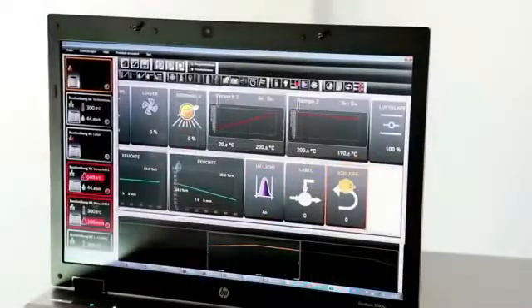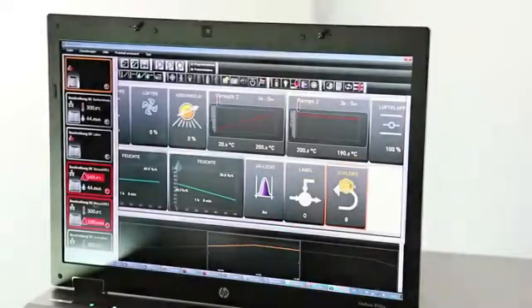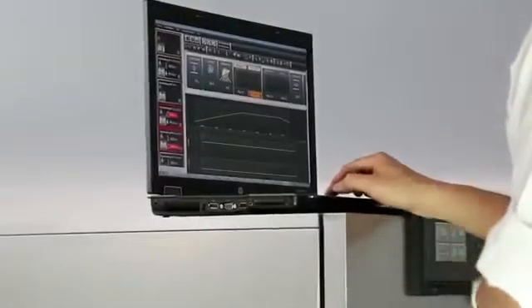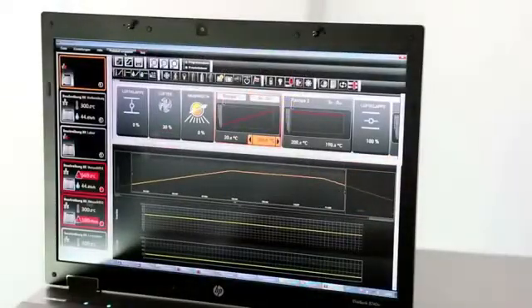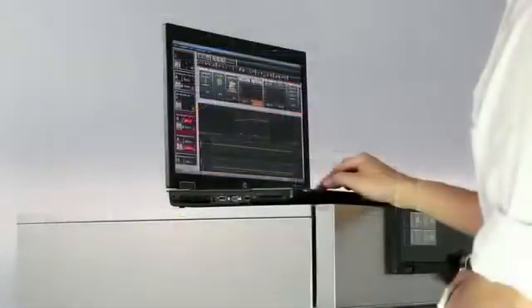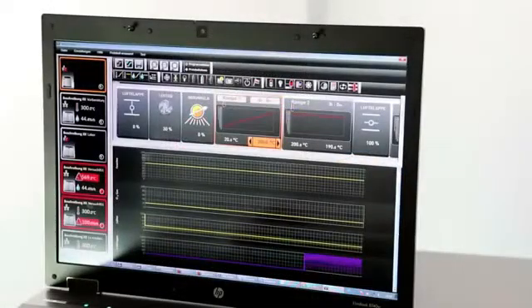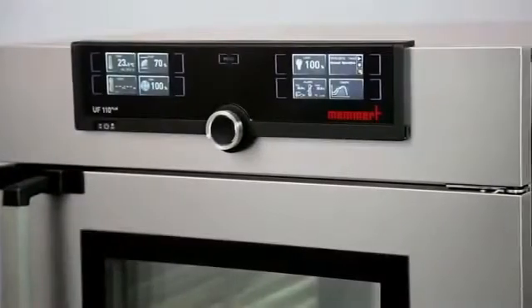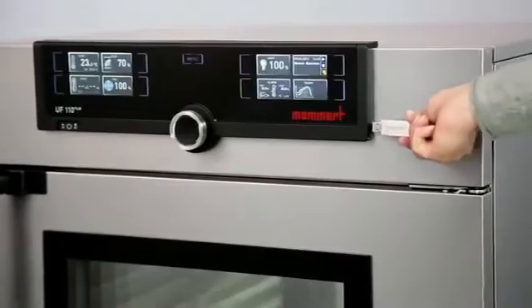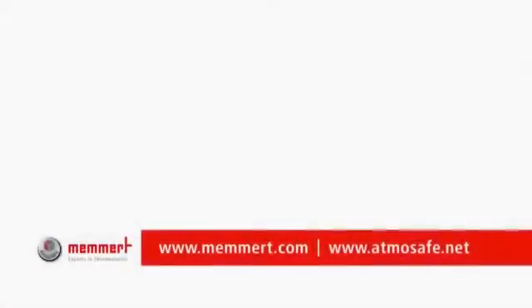Repeat functions can be inserted in any place within the program sequence. And to give you a good overview, AtmoControl shows the process sequence graphically while you are programming. When your profile is completely programmed, simply upload it via USB stick or Ethernet connection.